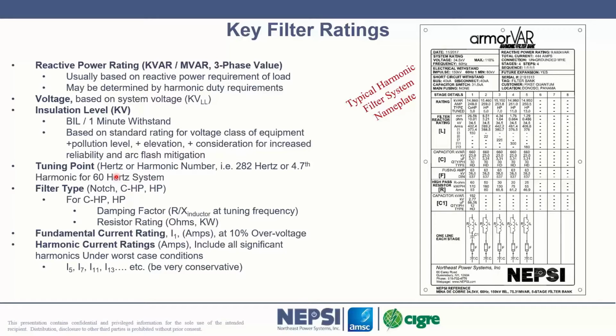There are three main types of harmonic filters being used in major industrial plants, and this includes renewable power plants also that we're involved with: notch, C-high pass, and high pass filters. They are the three types of filters. When you supply a C-high pass filter or a high pass filter, you have what's called a damping factor associated with it, and that's equal to the R over X at the tuning frequency. And I underline that, tuning frequency.